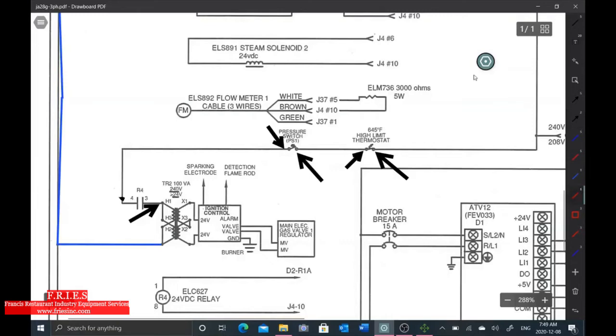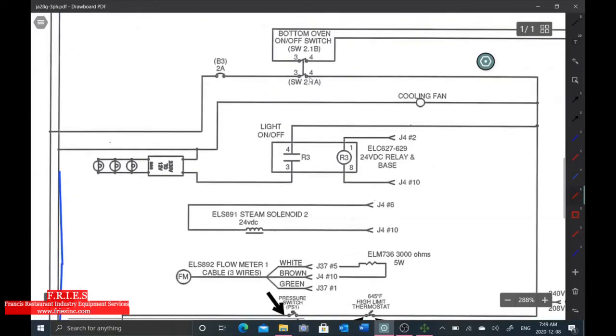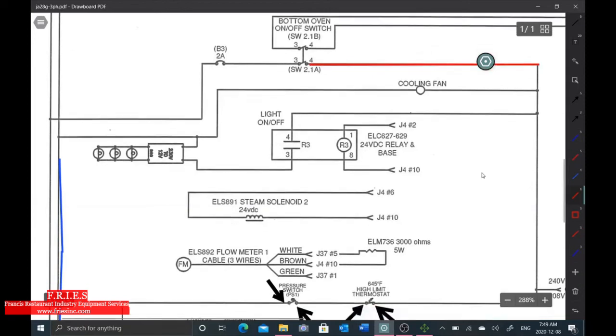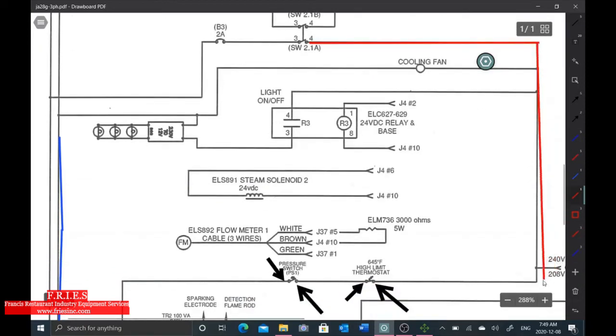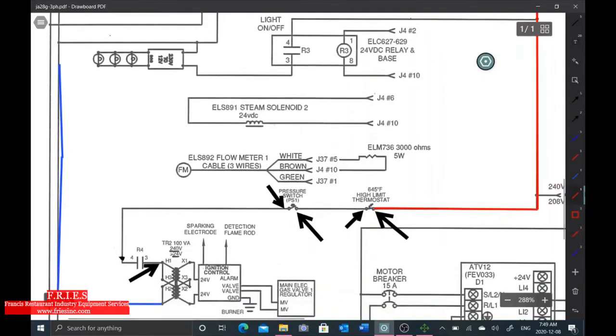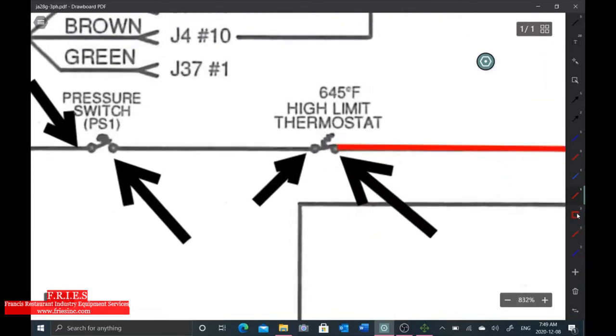So what does that mean? That means we can draw our line right through. Okay? I have power right at this point here. Okay? I do not have power at the outlet on this test point. I can't see that too well. I do not have power on this side of the switch. Okay? So what does that mean about this high limit thermostat? It means it's in the open position. Okay? So anytime I have something in the open position, I always test across.